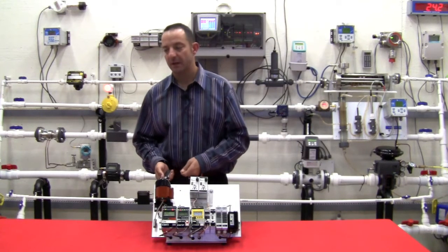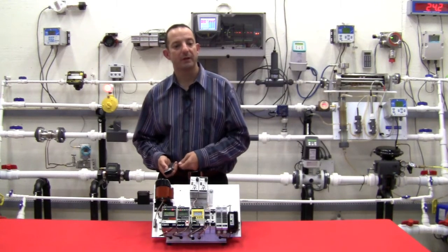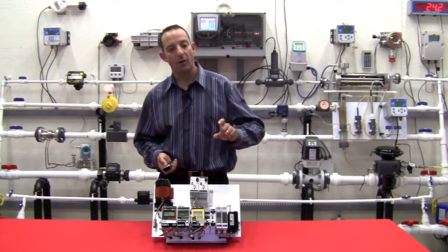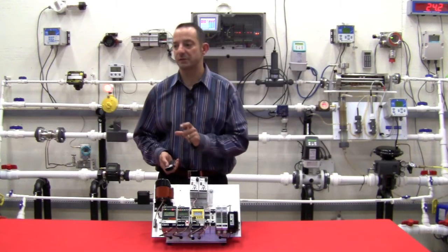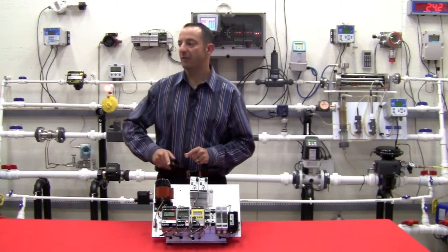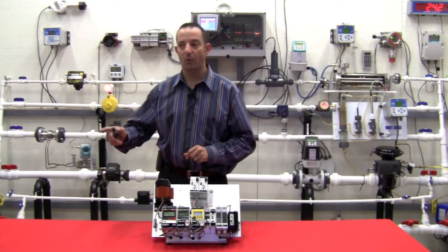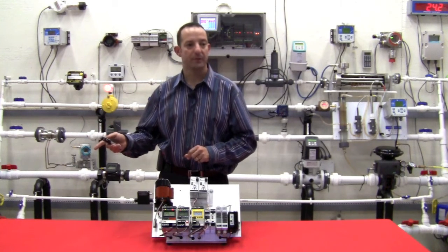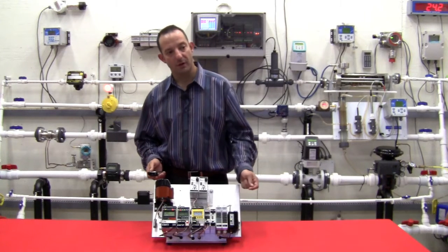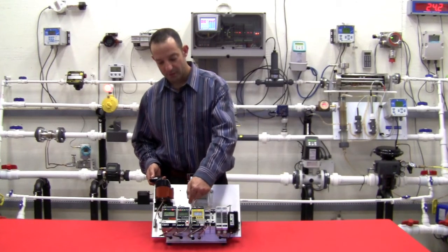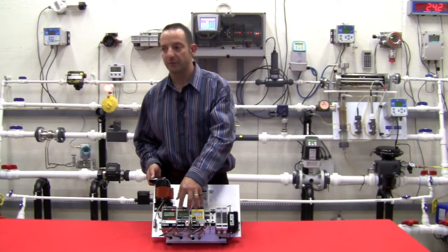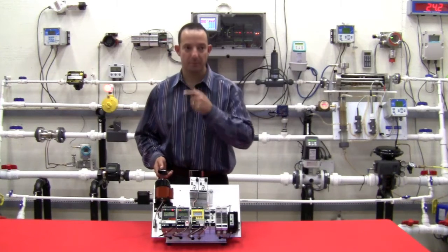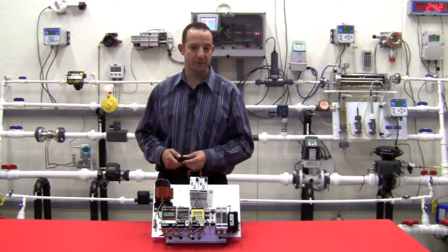Also emphasize that many of the alarm trips are available with an analog output option, which can reproduce all or a portion of the input signal and send a 4 to 20 milliamp current or a voltage signal over to a control system for monitoring, so that you could have a signal come into the alarm trip unit for a safety function, but then also be sent over to the control system for monitoring purposes.